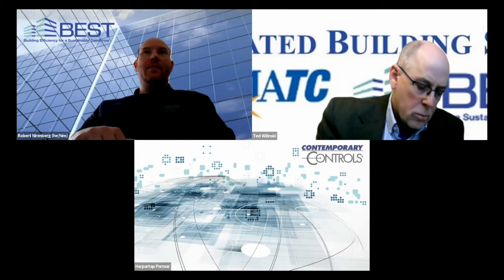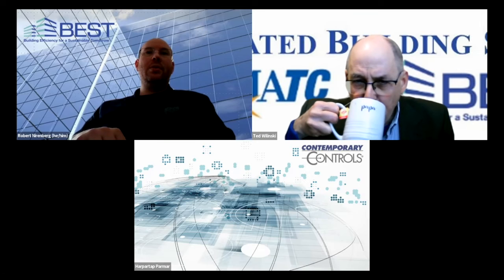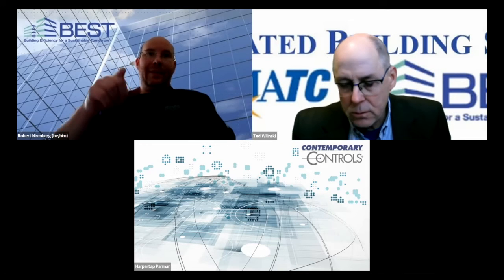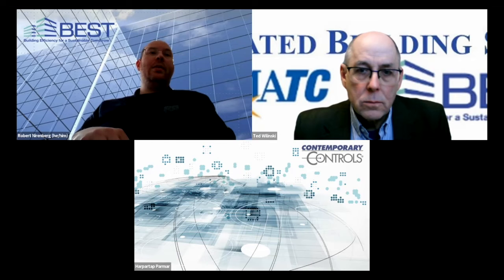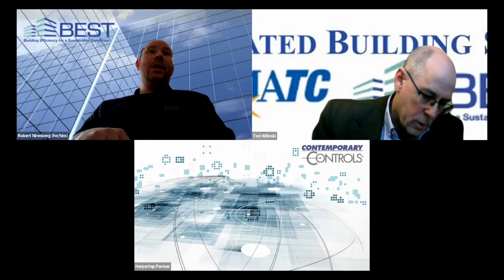And it really is. But Modbus is an older communication, but it's no less valid. And it's so heavily used. It's everywhere. It's in every controller, every device. It's in every industrial network in the world. And it's really heavily on the industrial side. If you need to communicate with a boiler, that's one of the greatest examples. There are very few boilers that actually talk BACnet, but there's a vast number of them that talk Modbus. And almost every modern control system has the ability to work with that.